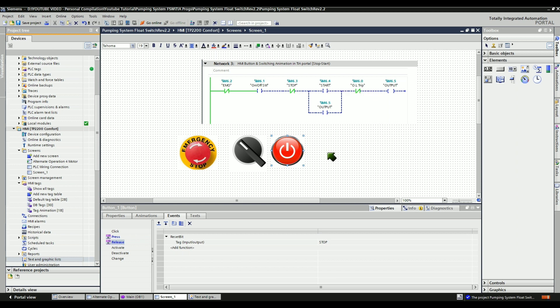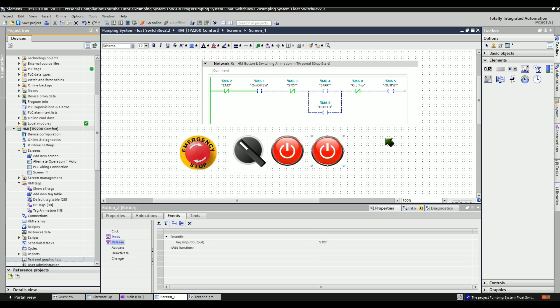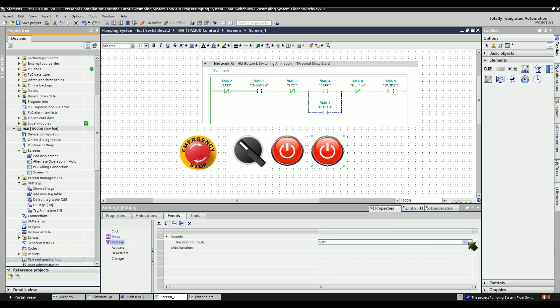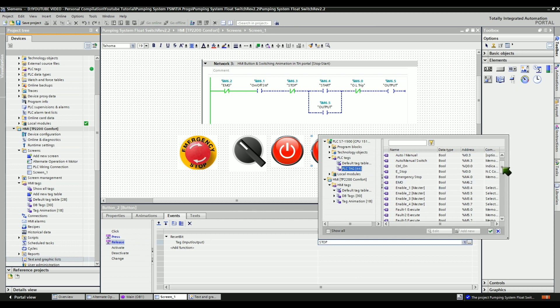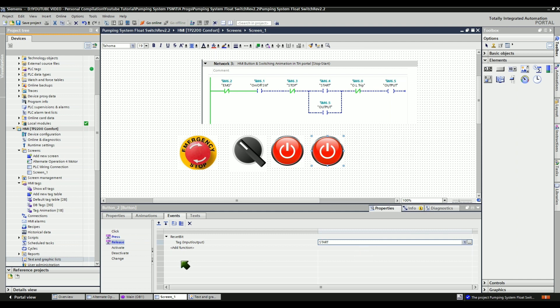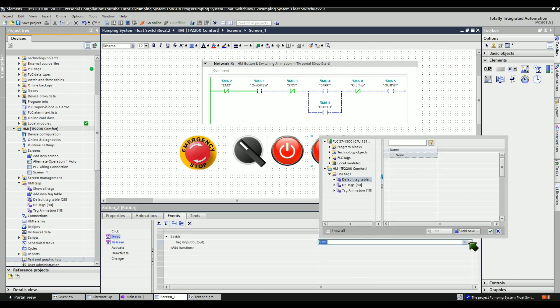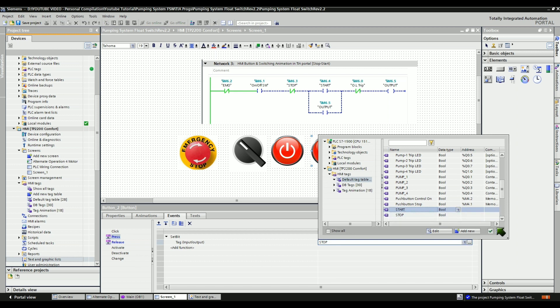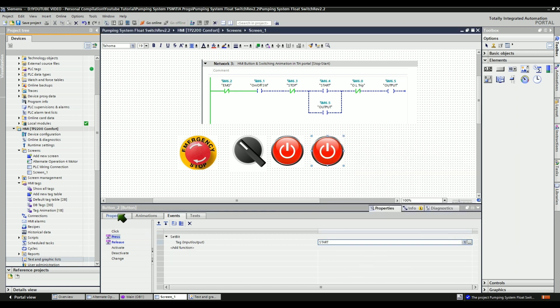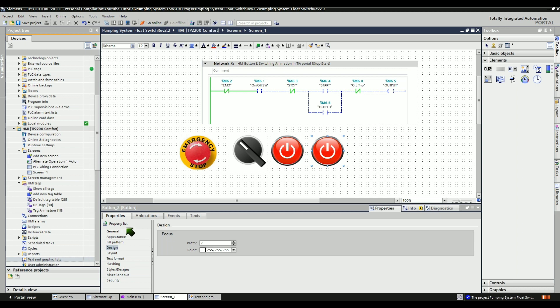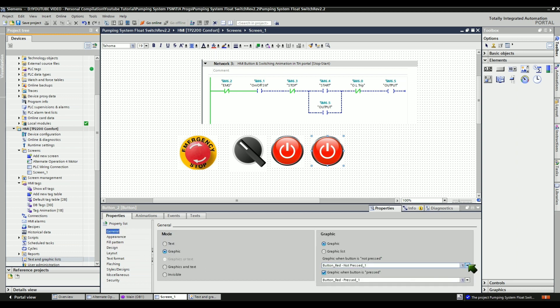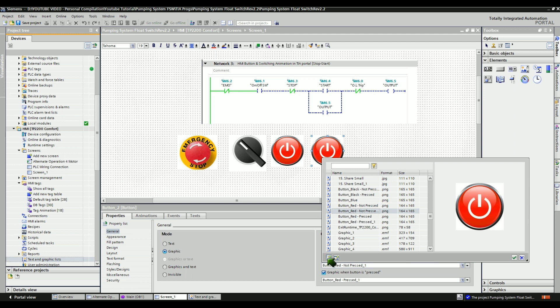Let's create a new one for the start push button — it's the same method, just copy the previous button and change the correct configuration. Let's configure the event functionality as a start push button. In the configuration, only change what is necessary. The global tag of the start push button is M6.4 memory bit. Let's replace the graphic when the button is not pressed and when the button is pressed.